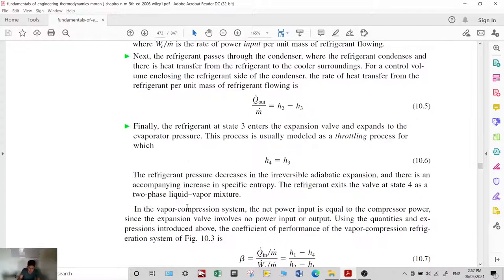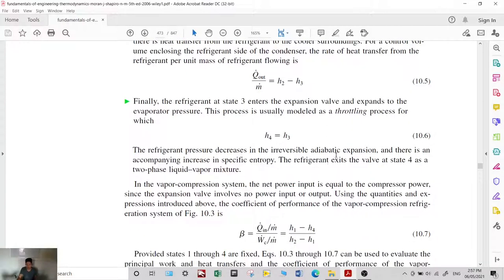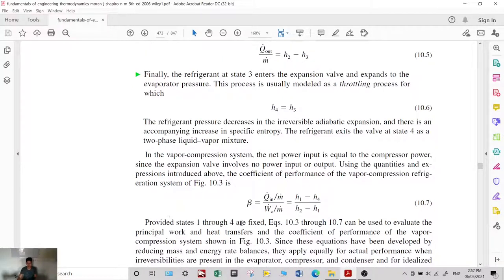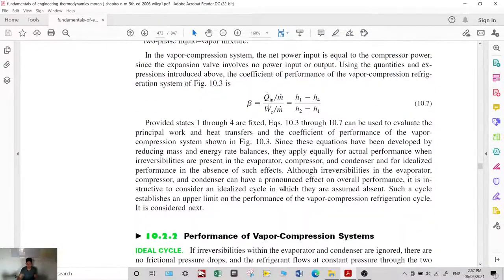In the expansion valve, the refrigerant pressure decreases in an irreversible process, with an accompanying increase in specific entropy. The refrigerant exits the valve at state 4 as a two-phase liquid-vapor mixture. The coefficient of performance beta is equal to Q in over the compressor work — since there is no turbine — equal to (h1 minus h4) over (h2 minus h1).